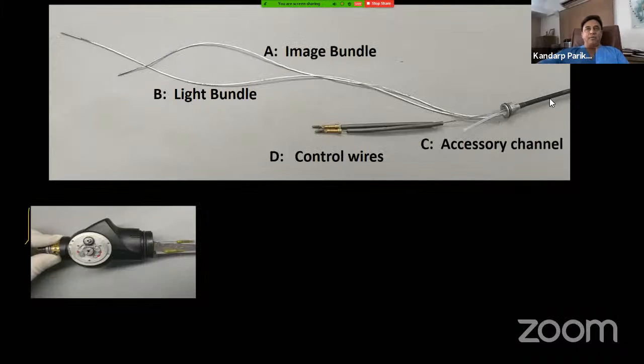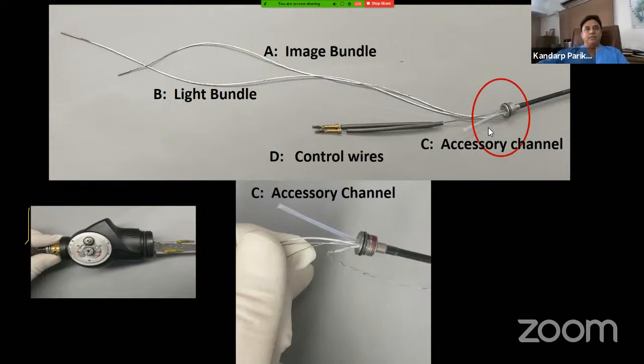This is the part of the shaft, and it has five components. There are these thread-like structures, two structures that you see. One is an image bundle and the other is a light bundle. The image bundle carries the image and the light bundle carries the light. There is this straw-like structure that you see here. If you have a closer look, this is an accessory channel. And these two wires are the control wires, responsible for the deflection of the scope, coming from the tip of the scope and going right up to the handle.